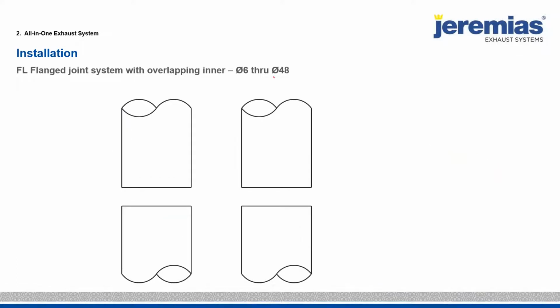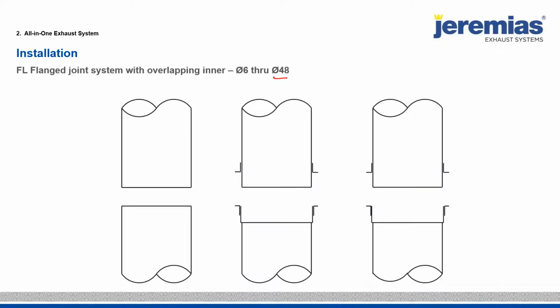Now on the larger diameters, up to 48-inch diameter, we go with a flange system like everyone else does, but we have a very unique twist on it. We expand one side, and then we add the flanges to the pipe on the outside of the pipe. So when you caulk the larger systems with silicone, and when you install the system, and then you install it with a V-band here, the flue gases or the condensate do not ever touch or influence the gasket. So this is the reason for this added or this extension of the inner.